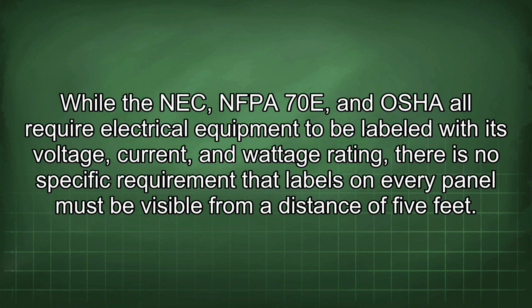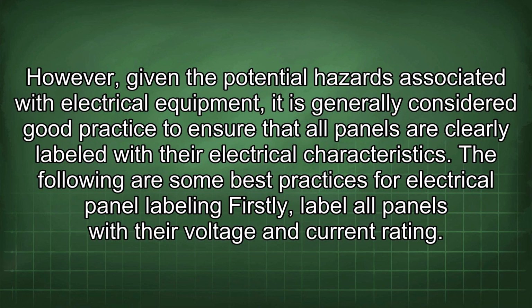While the NEC, NFPA 70E, and OSHA all require electrical equipment to be labeled with its voltage, current, and wattage rating, there is no specific requirement that labels on every panel must be visible from a distance of 5 feet. However, given the potential hazards associated with electrical equipment, it is generally considered good practice to ensure that all panels are clearly labeled with their electrical characteristics.